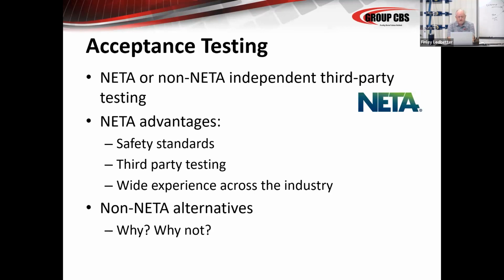The advantages of a third-party test are if you don't do the testing, then you don't have a starting point, okay? And you need a starting point. You need a base to build upon with your maintenance plan. Because if you know the equipment functioned properly day one, it's a real advantage when a year or two from now you get into timing tests and you realize that it slowed down. If you don't have the initial timing test to determine that, you don't know if it's an atmospheric problem, a lube problem, what it might be that's slowing down your breakers. So it's real important to get all this test data in the beginning.